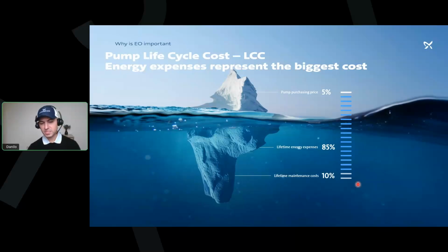Depending on how the pumps were sized for that application, how they're utilized, and how they're maintained, the maintenance costs can start going higher and lower, and that already tells us what's happening with the pump. But the main focus of our conversation today is lifetime energy expenses. It represents about, I want to say, 80% of the pump's lifetime cost. And that's all based on an average, because depending on the location and the cost of electricity, the energy expenses could represent a bigger number than that.